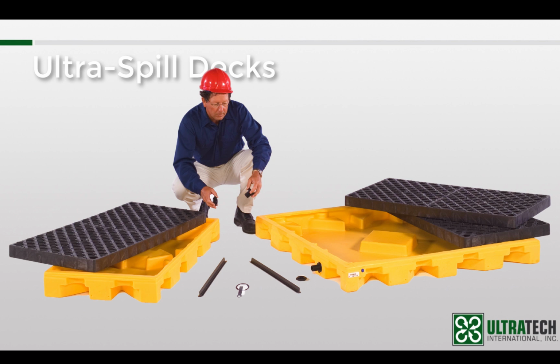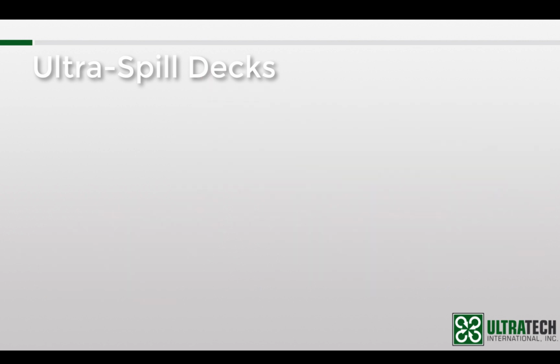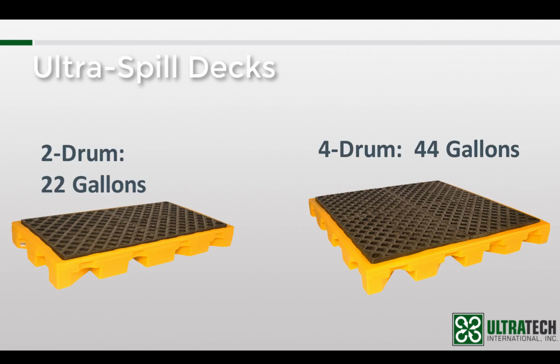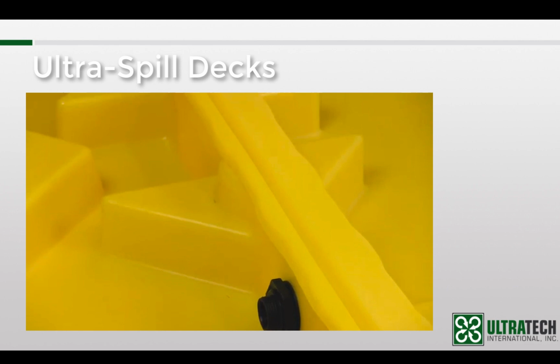You can see that none of these units have enough capacity to meet the regulations on their own. So as I mentioned a moment ago, they need to be connected in order to achieve the required capacities. One common configuration is a 2-drum spill deck connected to a 4-drum spill deck. Those 2 units combined will provide a total capacity of 66 gallons, which is enough to meet EPA and SPCC requirements. This configuration would require 2 bulkhead fittings.